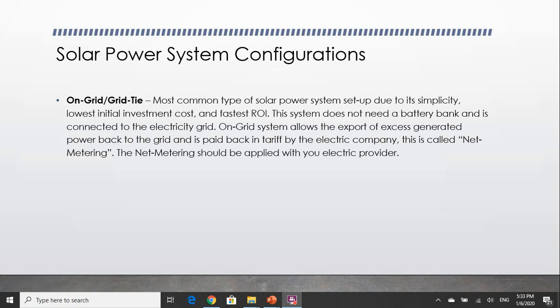As you are able to export your excess power back to the grid, you also don't need a battery bank. But the catch is you still need to connect your system to the power grid. Thus, this is not applicable for remote areas. And in case of a power disruption, you won't have power as well. The reason being is that during blackouts, you should not be exporting power to the grid, as the repairman from your electric company might get electrocuted.